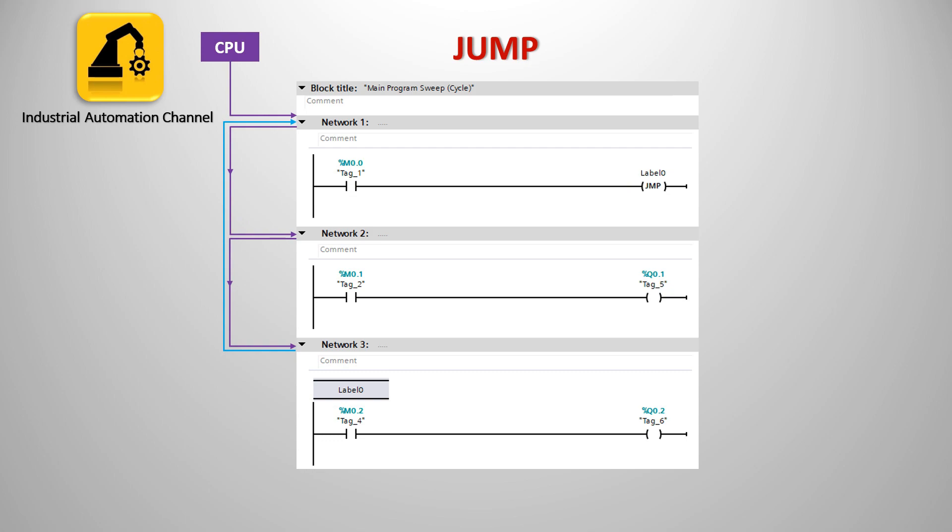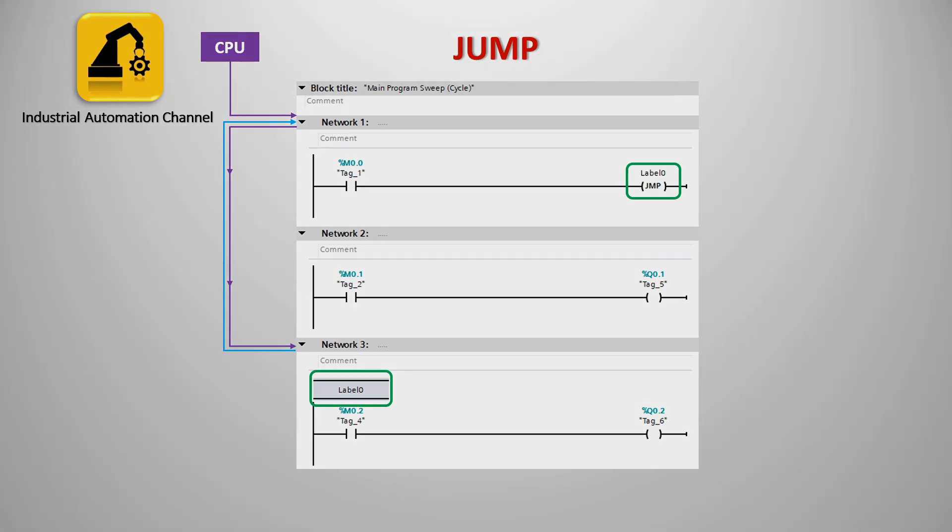The output Q0.1 will be true when M0.1 is true and at the end the third network will be run. But if I activate the jump, the second network will not be scanned by the CPU and if M0.1 even gets a true value Q0.1 will not be on. Let's create this program in TIA Portal and see how jump instruction works.